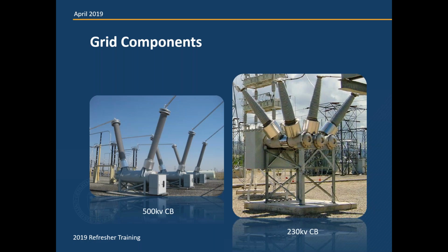Here's an example of a 500 kV breaker. This is at one of our stations here in Northern California, and you can see it's a three-phase electrical system, and the one on the left, they're all the same circuit breaker, but look at the distance between them. I said earlier, the higher the voltage, the more space you need between the conductors, because you don't want them too close because they'll flash over and short out on each other. So that's one circuit breaker. And again, it comes in from the left, goes down through that bushing. The conductor goes through the middle of that bushing, through the bottom of the tank, where there's a bunch of contacts. That's what we call an SF6 breaker. And it pops up and goes out to the right and it heads on down the road. Over on the right is a 230 kV breaker, and you can see it's all in one nice little neat area. Next slide, please.